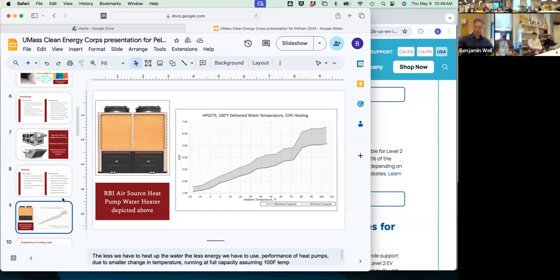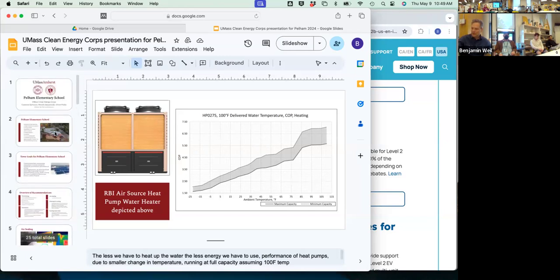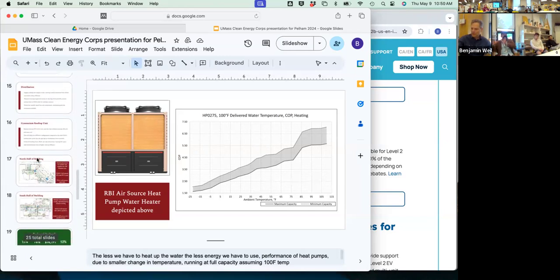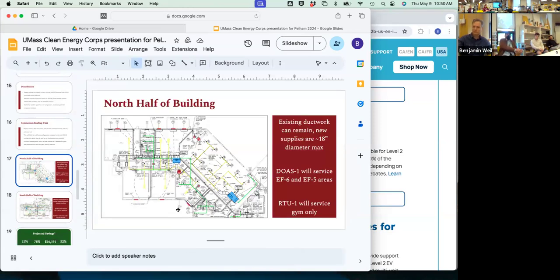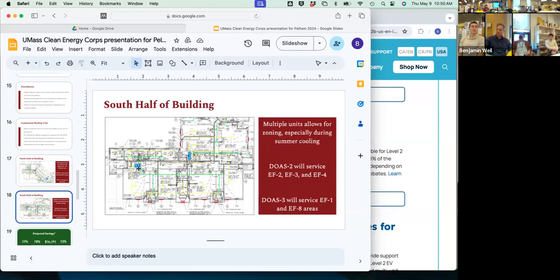I think you probably already covered this, but I forgot, do you have a sense of how many enthalpy recovery ventilators we use? I understand the gym is standalone, and then there's the rest of the space. Yeah, so we have the one in the gym, like you mentioned, and the one for the north side of the building, a few of the classrooms plus the cafeteria up there. So one for that whole wing. I believe that's a 4,000 CFM unit, which is a little bit higher than the two in the south half of the building, which are like 2,000 and 3,000.